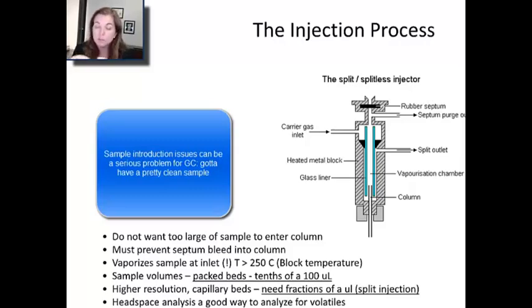There's a temperature that you can set for the injection system, and that can vary from method to method depending on the boiling point of the analytes you're most interested in. The other thing this diagram indicates is split versus splitless injection. In a split injection, you might be injecting 50 microliters, but the system only opens up for a portion of that time to take, say, 1/50th of what you injected. You'll see it expressed as 1-to-10 or 1-to-50. That's an important terminology — the difference between split and splitless injection. Split injectors have become standard on GCs because of the advent of capillary columns that are so small you can't really load a lot of material into them.